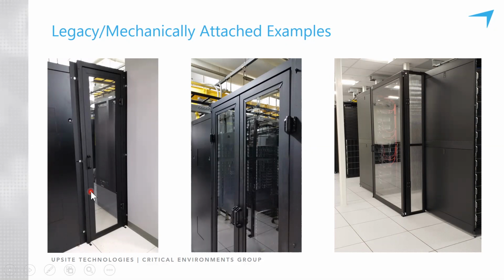So there can be either a single swing door like you see on the left. These are sometimes more custom sized for specific gaps. If you look at this one, it's going between a column and a rack, but it may even be just a share over, or 24 inches wide. So that was a custom door that was made. People need to get in and out of that space. You see double swing doors in the middle, and then there's sliding doors. Sliding doors are very common, and they can come in single or double wide flavors as well.